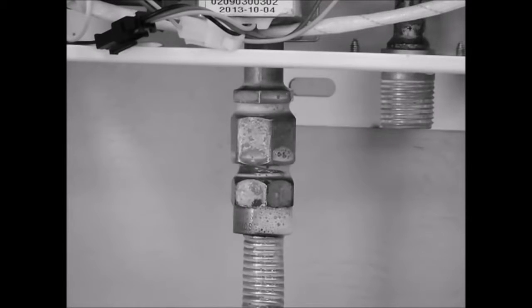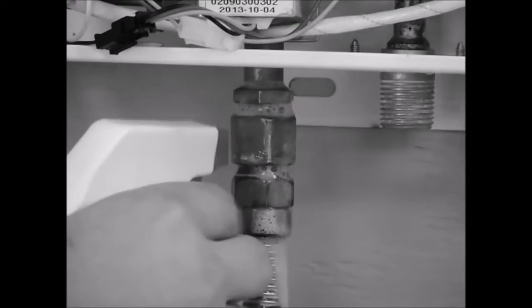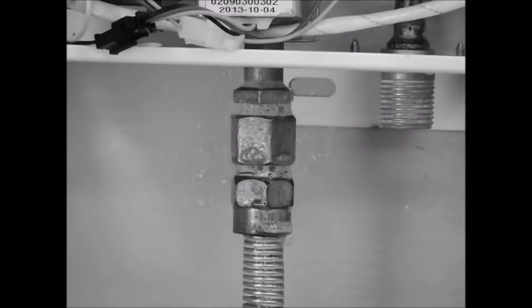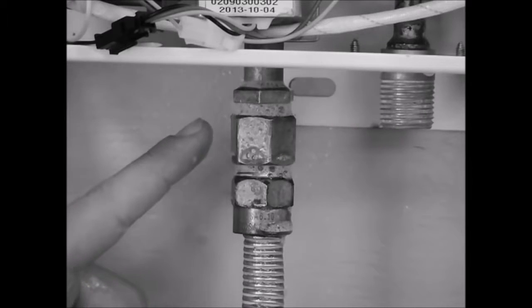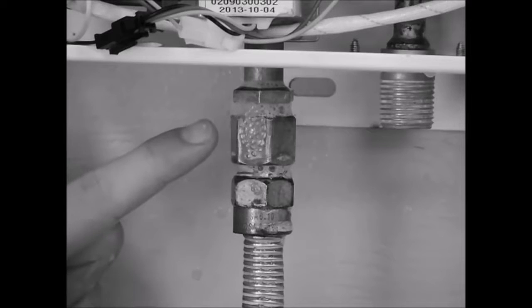Next, confirm you have appropriate gas pressure, which is a minimum of 0.41 psi or 11 inches of water column. Lastly, check the connection with soapy water or glass cleaner for a leak. Bubbles will form if a leak is present. Please correct and retest if necessary.